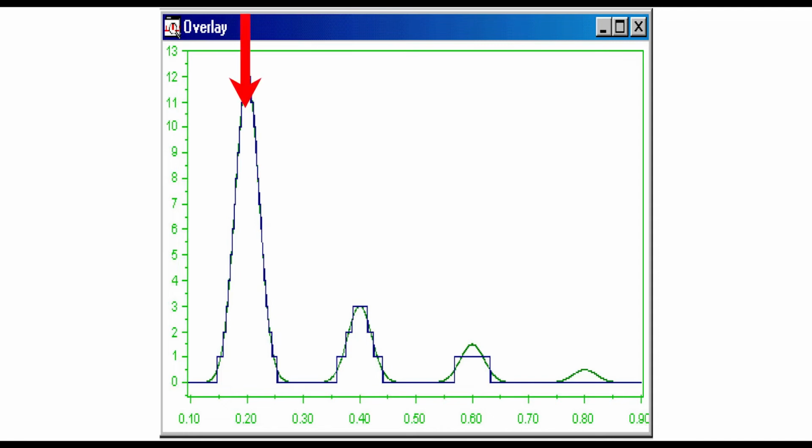The first peak is 12 steps high and will be accurately quantified. The second peak is borderline, and the third is highly distorted. The fourth is smaller than the step size, so it has been rounded down to a flat baseline and disappeared from the quantified chromatogram.